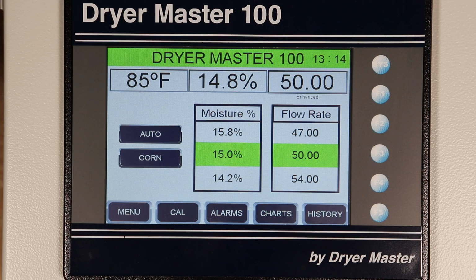The key points to remember are where you set your moisture trigger points and what rates you want to run at. And those are things that can change day to day. It can change based on the product you're drying. It can change based on the drying conditions. It can change based on the residence time of your dryer or what kind of inlet moisture you have coming in. Okay, these are all things that you have to consider when you set this.